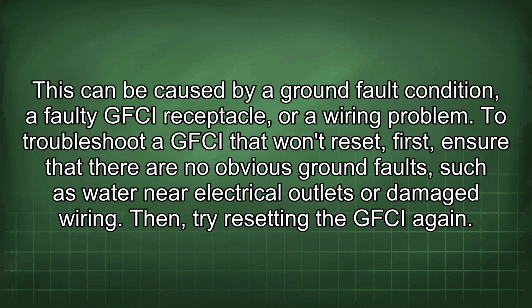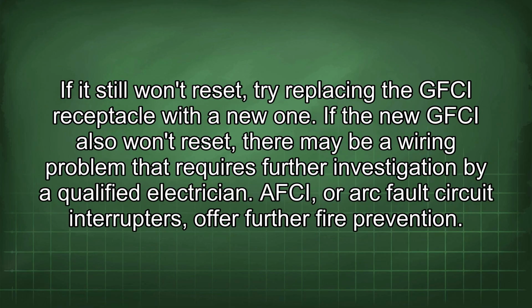Another common issue is a GFCI that won't reset. This can be caused by a ground fault condition, a faulty GFCI receptacle, or a wiring problem. To troubleshoot a GFCI that won't reset, first ensure that there are no obvious ground faults such as water near electrical outlets or damaged wiring. Then try resetting the GFCI again. If it still won't reset, try replacing the GFCI receptacle with a new one. If the new GFCI also won't reset, there may be a wiring problem that requires further investigation by a qualified electrician. AFCIs, or arc fault circuit interrupters, offer further fire prevention.